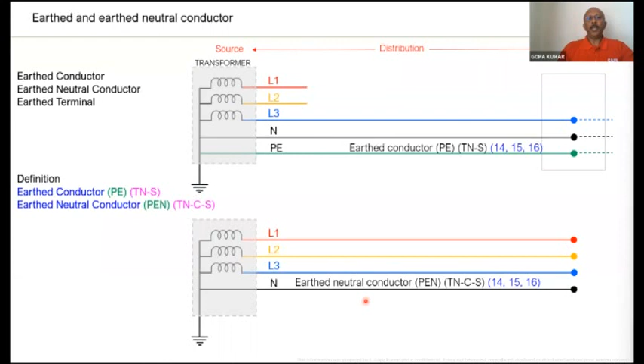We are supposed to get a wire, the 5th wire. This is called an earthed conductor. That means the network is a TNS network, regulation 14, 15, and 16. The regulation also says earthed neutral conductor. What does it mean? It is a PEN conductor. That means at the consumer premise, you have to make a link and you have to make an earthed terminal. So basically, the regulation explains about a TNS network or a TNCS network.